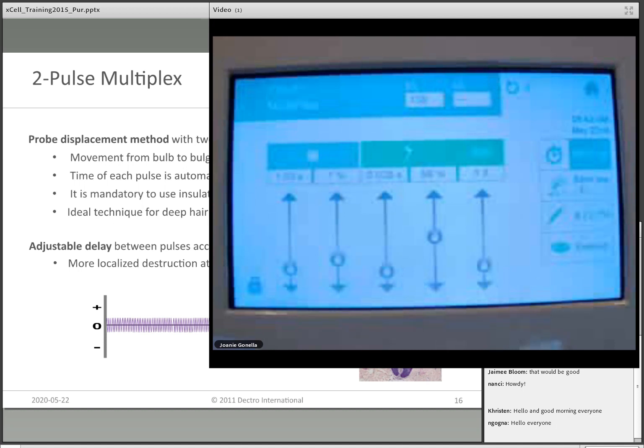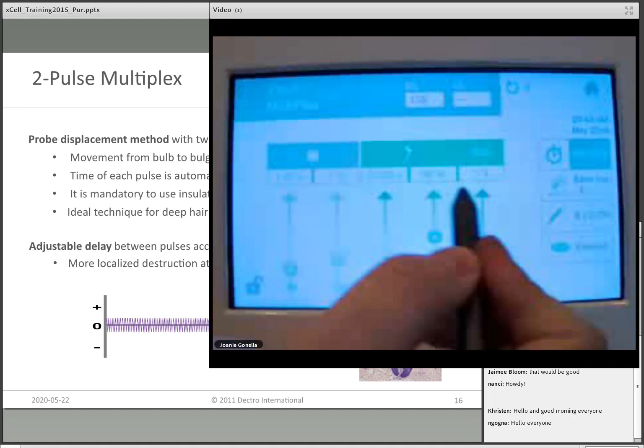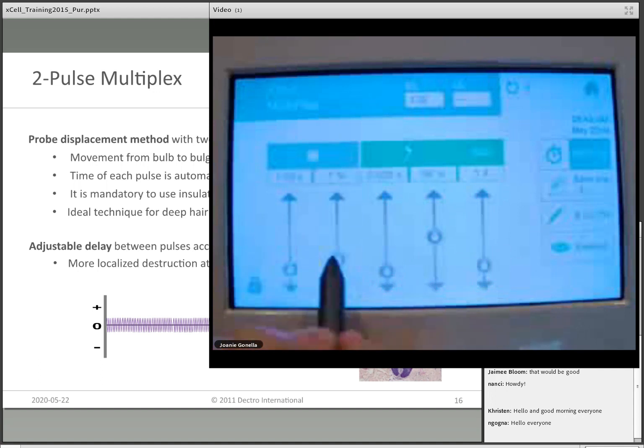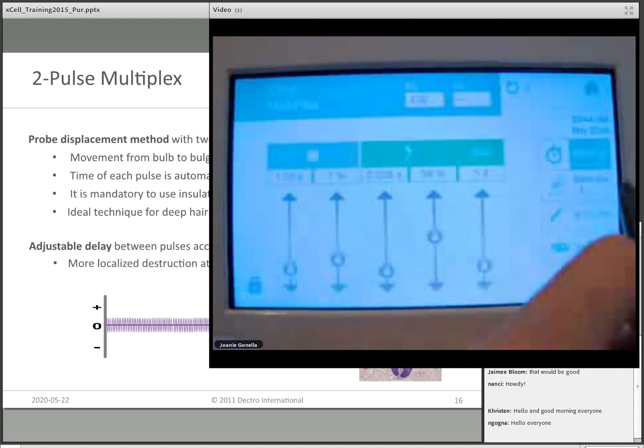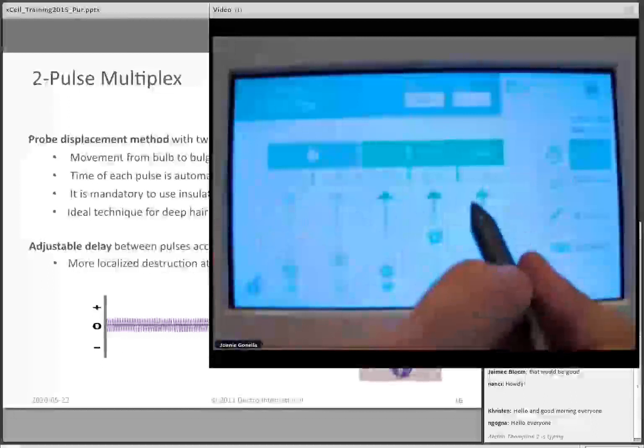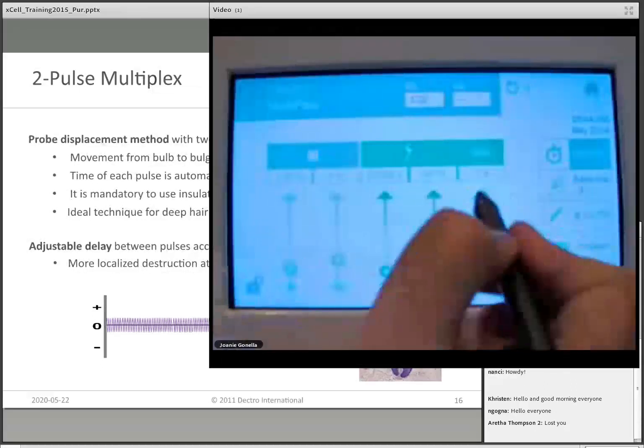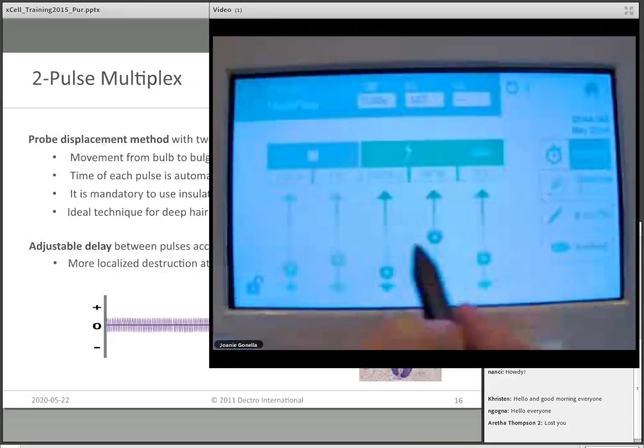So that would be without changing it. Now, if I want to do this, by the way, you have to unlock when you want to mess with the settings here. You don't have to unlock it if you're just going to go and change a preset. But to change the settings as far as the time, the intensity, the pulses, you have to unlock your padlock. Move it up to 2, and I'm going to lock it again. Now, press and hold it down.